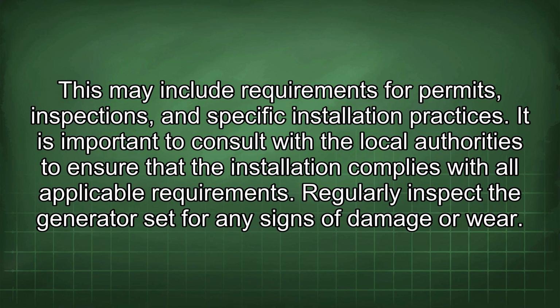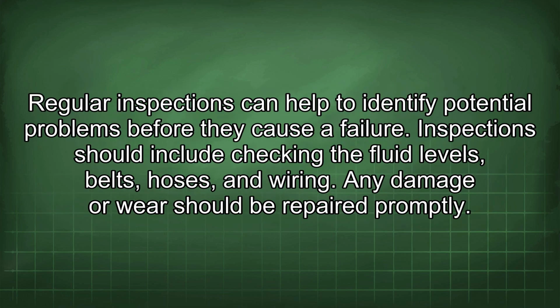Regularly inspect the generator set for any signs of damage or wear. Regular inspections can help to identify potential problems before they cause a failure. Inspections should include checking the fluid levels, belts, hoses, and wiring. Any damage or wear should be repaired promptly.